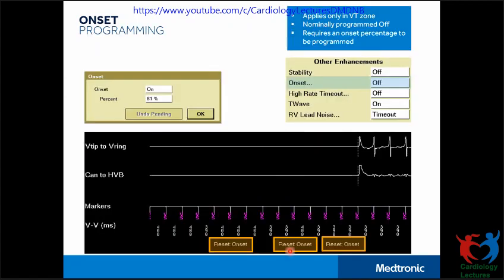The onset feature operates in the VT zone only and is nominally off. When turned on, we also have to program the percentage. During an episode, the device continuously analyzes the average of the current four ventricular intervals compared to the average of the previous four ventricular intervals. It compares the difference between these two average rates to the programmed onset percentage. If the percent change is greater than the programmed percentage, the onset criteria is met and VT is detected.